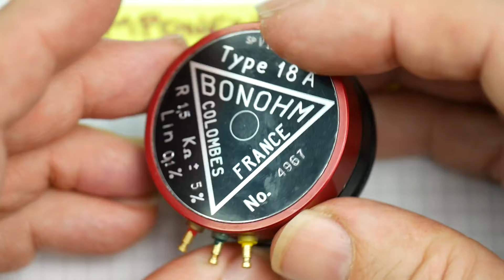And not only do we get the serial number, we also get, as proof of that, the calibration certificate. And this is the calibration certificate for this particular pot. There's the serial number there, 4967. There's the parameters, the linearity and the nominal resistance. But we've also got a little, I don't know if you can see that, near to the central 0 mark, which is the precise resistance that we expect at that rotation as a pot. And the limits there, you've got plus and minus 0.1%. A little green line going around there. There it goes all the way around.